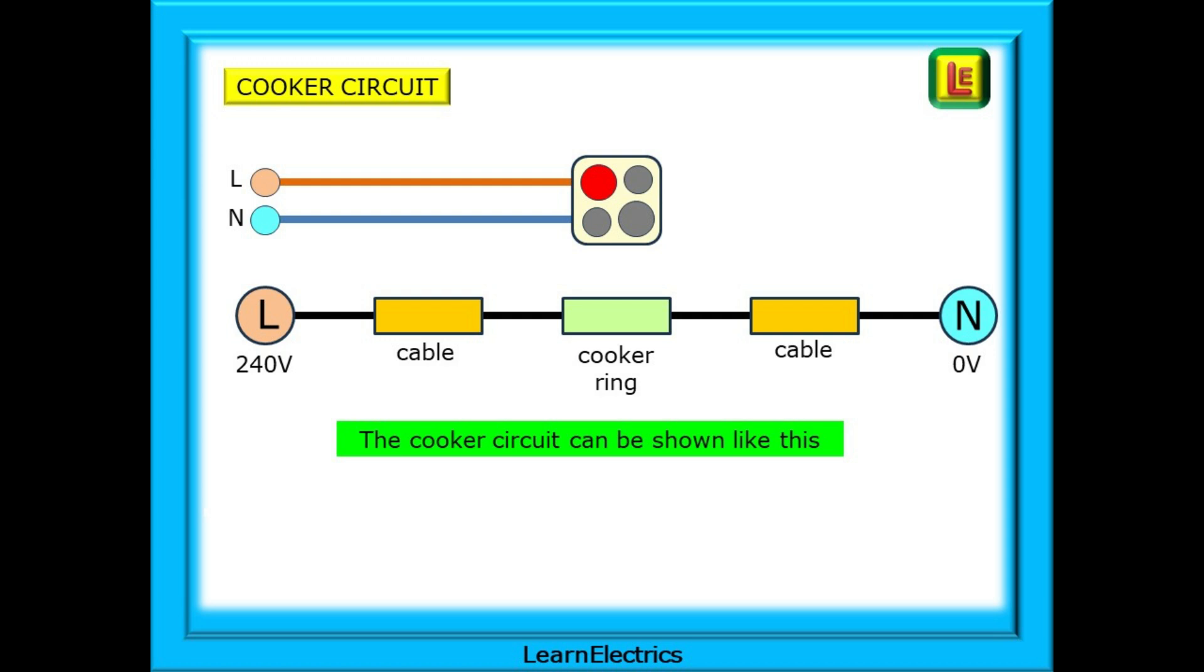The same circuit can be shown as one long string as shown at the bottom. The calculations will be based on DC resistances. The difference in AC impedances is very small at 50 hertz. And for most of the calculations, we will use 240 volts as it often makes calculations easier. For some examples, we will use the 230 volt nominal voltage as per the regulations.